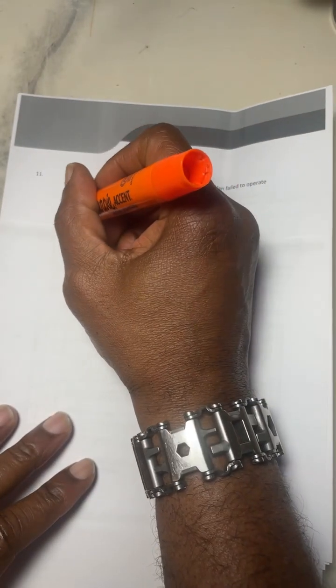11, let's see. In the heat pump operating in the heating mode, if the indoor fan failed to operate while the thermostat was calling for heat, what would happen? A, the outdoor coil will ice up. B, the indoor coil will ice up. C, the low pressure switch will open. Or D, the high pressure switch will open. Yeah, that's D. The high pressure switch will open.